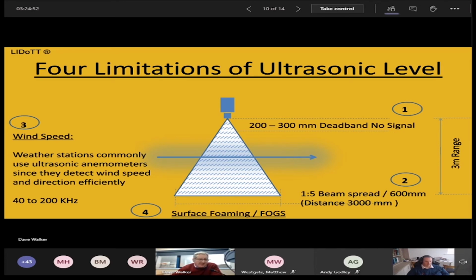And the only real way to do that, well, two ways, is either to increase the power, which can cause a couple of problems because if it's a battery operated system, then you've got limitations on power and longevity of life before changing the batteries. But also, if you increase the power too much, you have what's called ringing effect, and I've got a slide showing the ringing effect in a bit. So you can't increase it too much. The other way is to lower the sensor much closer to the target of measurement, so you're getting all the energy focused and returning back to the ultrasonic sensor itself. But again, the limitation of placing an ultrasonic close to the target of measurement is that deadband. Once there are surcharge conditions and the water goes into that deadband, the ultrasonic sensor is blind.